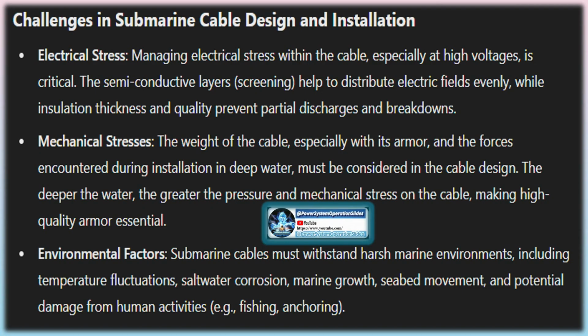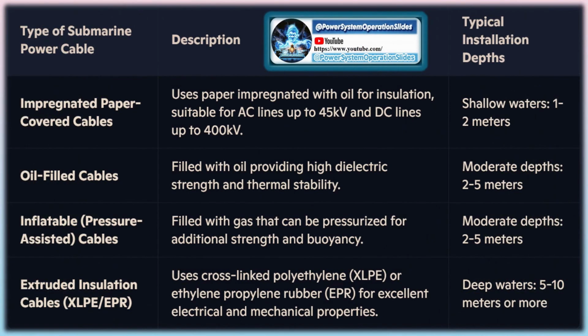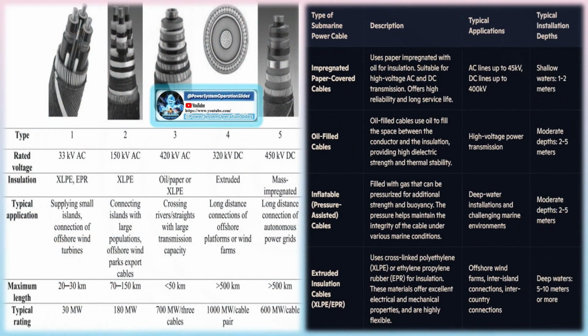Water ingress can degrade the electrical properties of the cable, so the water-blocking materials are essential to prevent any moisture penetration along the conductor. Conductor screening, semiconductive layer: extruded semiconductive material is applied around the conductor to evenly distribute the electric field and reduce electrical stress within the cable. This layer is crucial for ensuring that the cable operates safely without breakdowns due to high electrical field gradients.